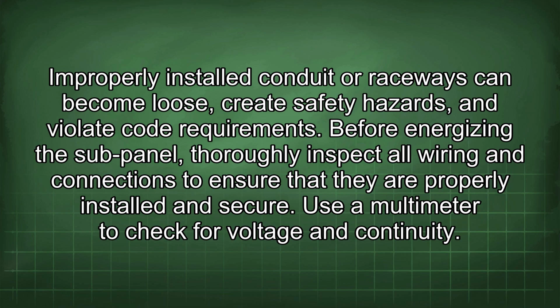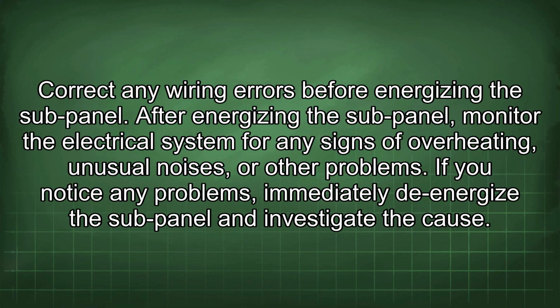Before energizing the sub-panel, thoroughly inspect all wiring and connections to ensure that they are properly installed and secure. Use a multimeter to check for voltage and continuity. Correct any wiring errors before energizing the sub-panel. After energizing the sub-panel, monitor the electrical system for any signs of overheating, unusual noises, or other problems. If you notice any problems, immediately de-energize the sub-panel and investigate the cause.